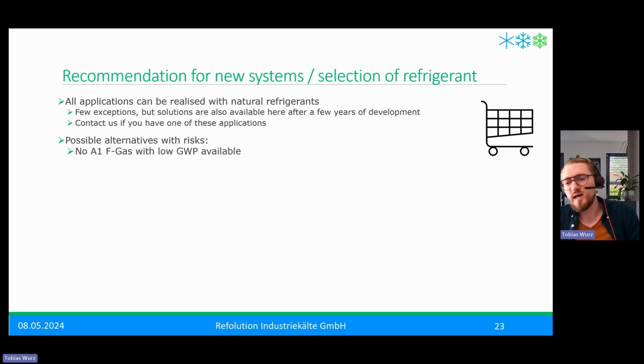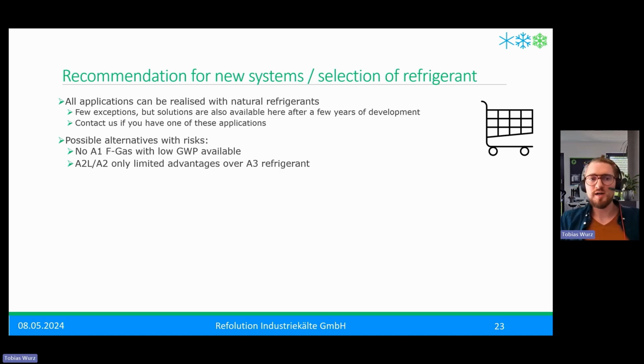Maybe for you to decide, because of course there are some alternatives or some marketing promises at the moment where some alternatives are promised. But to say it, there's no A1 F-gas with low GWP available. So all of the solutions now are A2L or A2. And these refrigerants have only limited advantages over A3 refrigerants. So for example, you could use an A2 with a lot of refrigerant or the same cooling capacity with A3 with optimized charge.